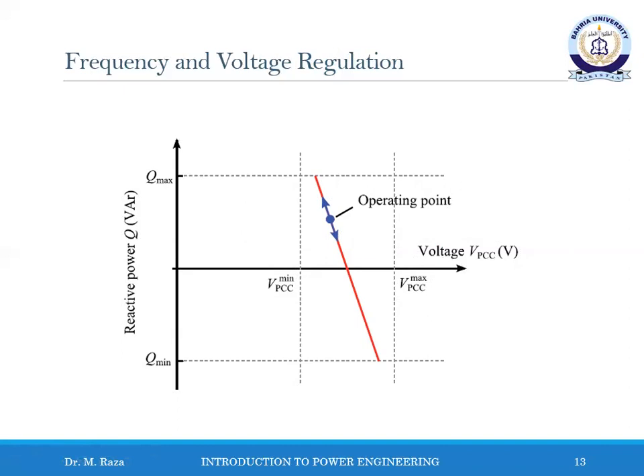In general, the reactive power requirement is usually expressed in three different ways. The Q control: in this control function, the reactive power should be controlled independently of the active power at the PCC. Power factor control: the reactive power is controlled proportionally to the active power at the point of connection, which results in constant power factor. And voltage control: this function controls the voltage at the voltage reference point by changing the reactive power injection. The reactive power control and voltage control functions are mutually exclusive, which means that only one of the three aforementioned functions can be activated at a time.